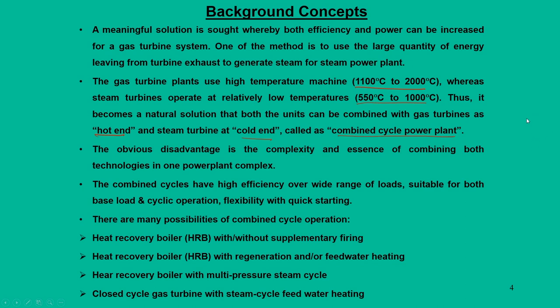Such combination has the disadvantage that it increases complexity and requires synchronization between gas turbine units and steam turbine units. However, combined cycles have high efficiency over a wide range of loads; they are suitable for both base loads and cyclic operations; and they have flexibility with quick starting. In case the steam turbine does not work, necessary power can be achieved from the gas turbines, and in peak load situations both units can work together to fulfill the load requirement.